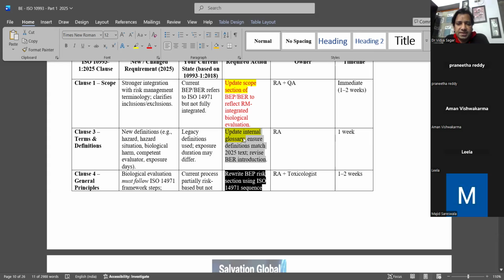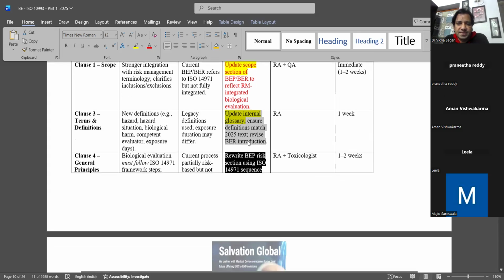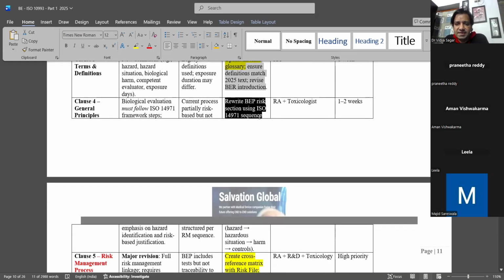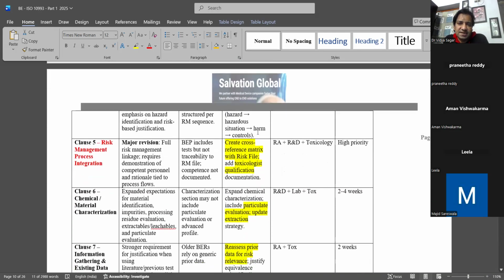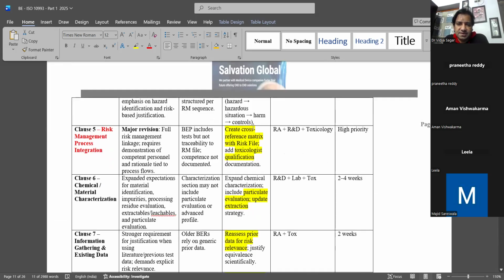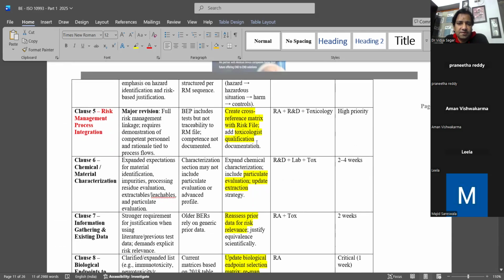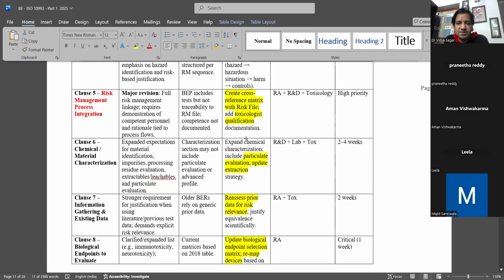Review the BEP and all this stuff. Integrate with the risk management. Rewrite the BEP risk and link it with the 14971 section, like I said: hazardous situation found, what are the risk controls. Cross reference it; I mean, refer, link it, and give a cross reference to risk management, stating that this has been included in risk management. That document has to be very visible to the auditor or for yourself: we have linked it, this is the document. And involve a qualified toxicologist. Many people can't find one, but at least use their CV and their signatures.